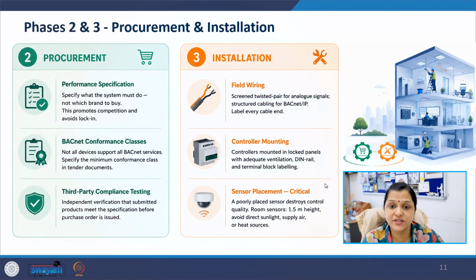Now let us discuss installation. Correct wiring practices are critical. Analog signals usually require shielded twisted pair cables. BACnet IP systems use structured cabling. Every cable should be properly labeled. Controller installation is equally important. Controllers should be mounted inside ventilated and secure panels. Finally, sensor placement must be done carefully. A badly located sensor gives inaccurate readings and destroys control quality. For example, a room sensor should not be exposed to direct sunlight or supply air.